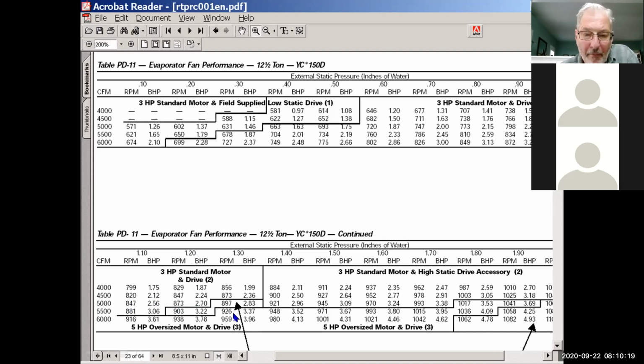Once I get above that 1.3 or 1.4, now I'm looking at a high static drive accessory, which is usually a pulley change. And if I get some really high statics, if I get up in this 2-inch range, now I might be looking at a 5-horse oversized motor to make that work, okay? So it all depends on the static on the system as to how we set these up. And that's kind of what this chart's telling us.